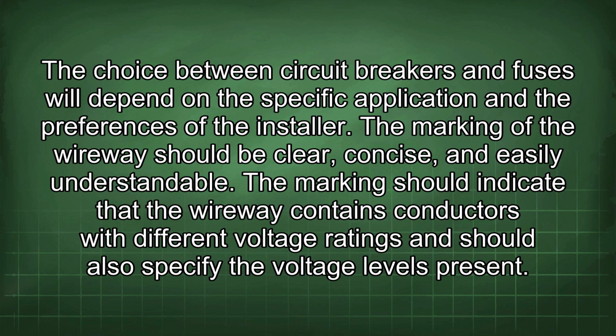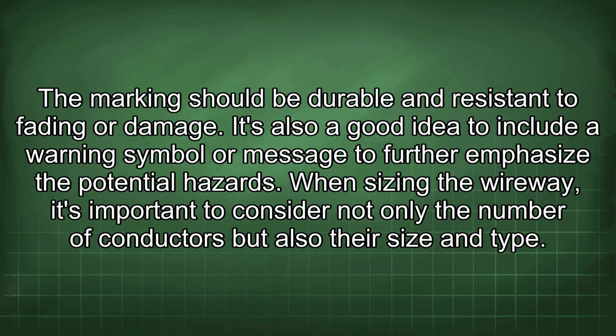The marking of the wireway should be clear, concise, and easily understandable. The marking should indicate that the wireway contains conductors with different voltage ratings and should also specify the voltage levels present. The marking should be durable and resistant to fading or damage. It's also a good idea to include a warning symbol or message to further emphasize the potential hazards.